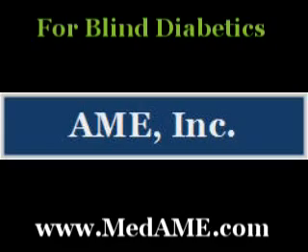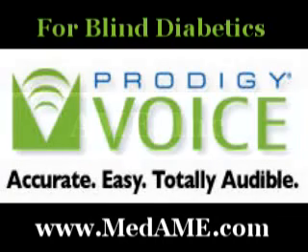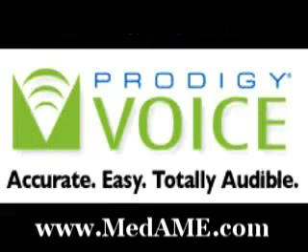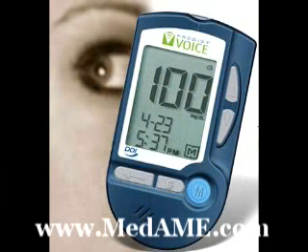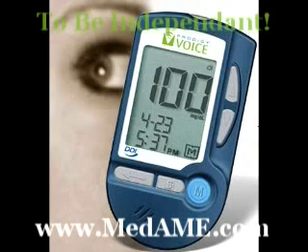The user will hear step-by-step setup instructions and hear their test results in just six seconds, with time and date, memory, and error codes. Tactile features allow vision impaired users to feel and locate the different buttons easily. The buttons have raised imprints enabling you to easily identify the buttons by touch. One of its best features is the repeat button, which allows the user to repeat the last message or test result at the touch of a button.